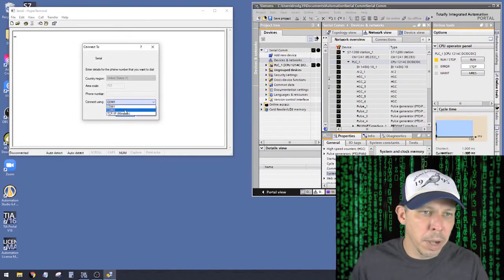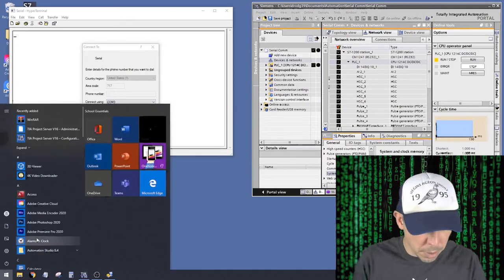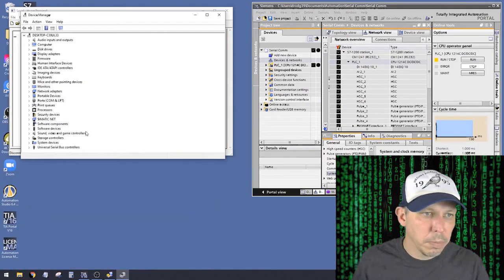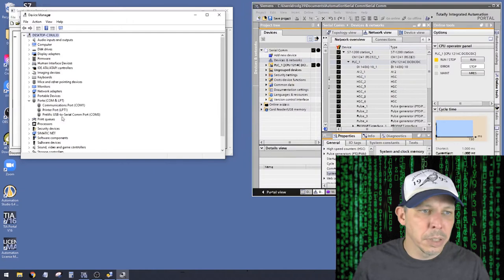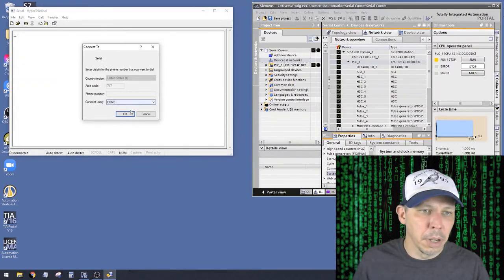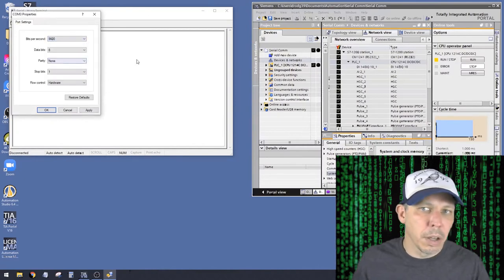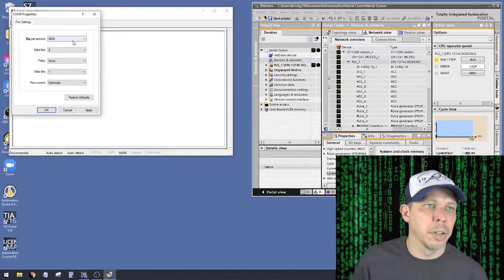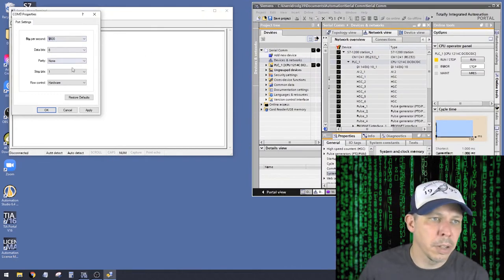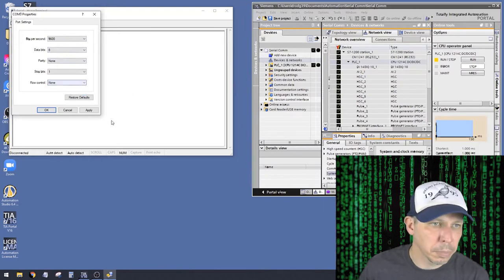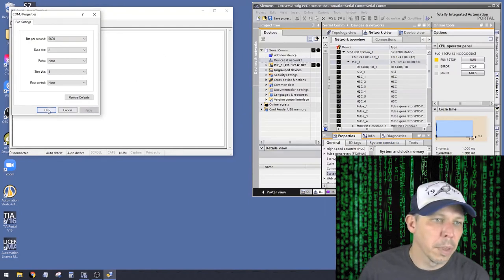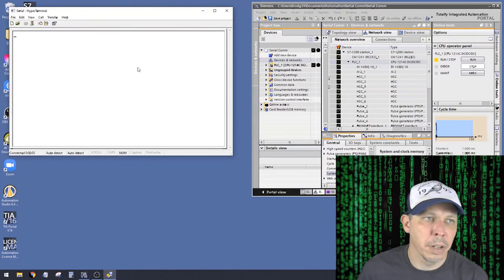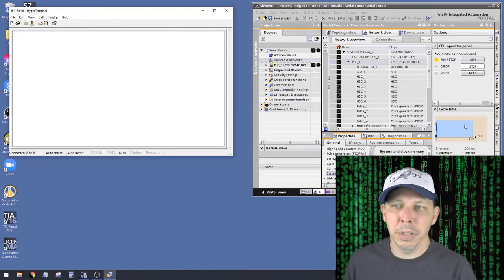New connection, I'll call it serial. I know mine's COM 3. The way you would know that is you go here and you type in device manager. You look at ports. So I know I have a USB to serial adapter and that's what I'm using on this. And it says COM 3 right after it. So that's how I know which COM to put in here. I know I have my card on my PLC set to 9,600, 9.6K Baud. And I know eight none and one is how I have it set up. And I have no flow control.